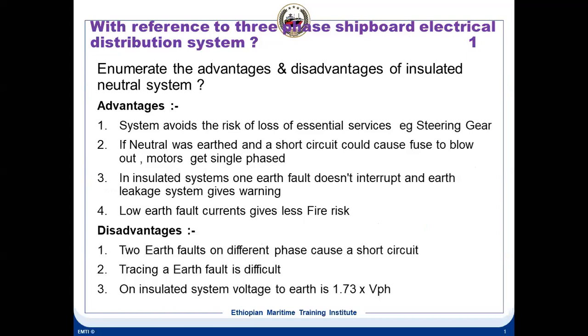With reference to three-phase shipboard supply, enumerate the advantages and disadvantages of insulated neutral systems. What are the advantages of neutral insulated systems? What are the disadvantages? The first thing is that it avoids the risk of loss of essential services, which was discussed in the last class, like critical machineries should run. That is a prime advantage for our marine part.